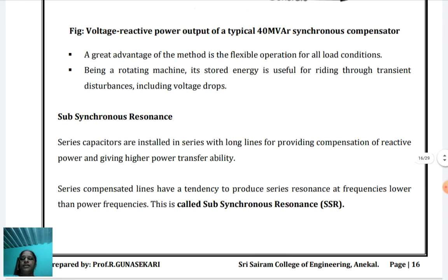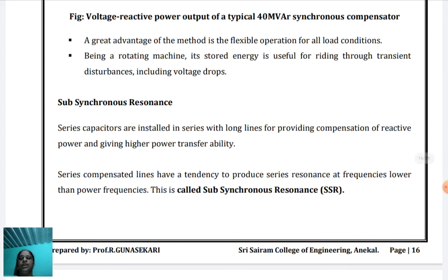Then next is sub-synchronous resonance. Series capacitors are installed in series with long lines for providing compensation of reactive power and giving high power transfer ability. Then we get sub-synchronous resonance. The definition of sub-synchronous resonance: series compensated lines have a tendency to produce series resonance at a frequency lower than the power frequency. This is called sub-synchronous resonance. The short notation is SSR only.